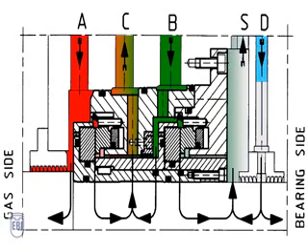In order to avoid any bearing oil contamination of the gas seal, the space limited by labyrinths or segmented carbon rings between the tandem gas seal and the bearing is buffered with nitrogen or air.